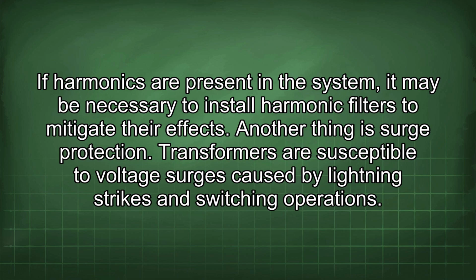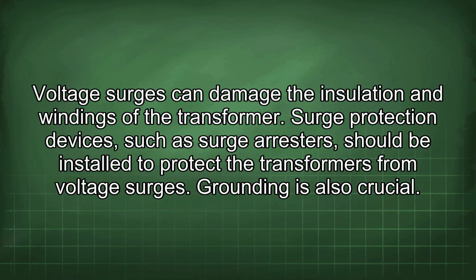Another thing is surge protection. Transformers are susceptible to voltage surges caused by lightning strikes and switching operations. Voltage surges can damage the insulation and windings of the transformer. Surge protection devices, such as surge arresters, should be installed to protect the transformers from voltage surges.